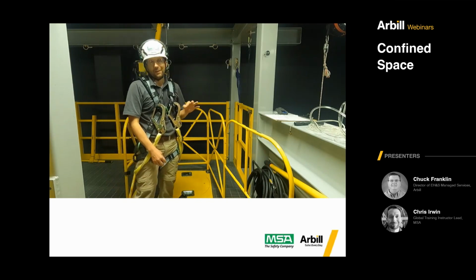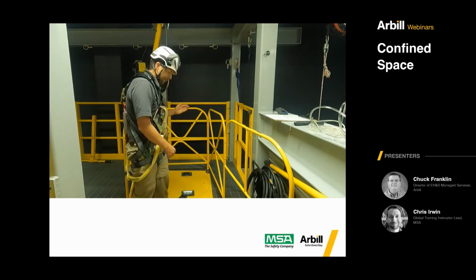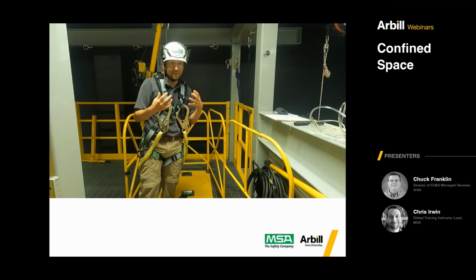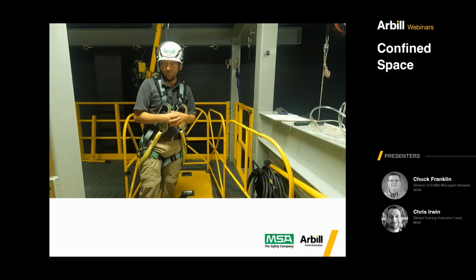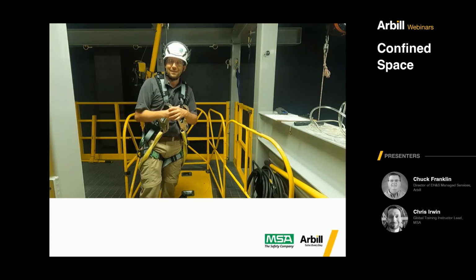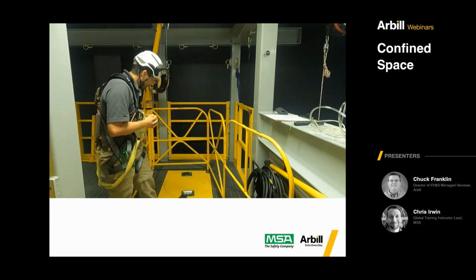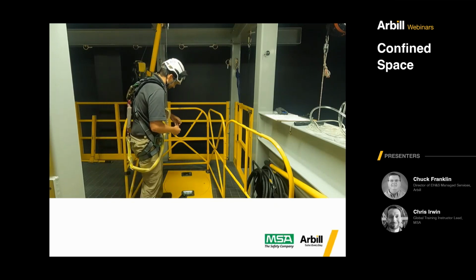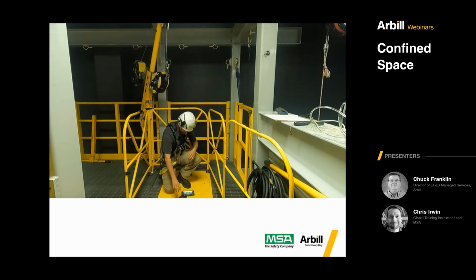I tell them if I find any kind of atmospheric reading at this point, things will probably be a lot more significant when we open the hatch. So it's not a bad idea to do a quick check. Now, I always ask my students, when I put the gas detector down here, how long do I need to wait to get a 100% or pretty close correct readout?